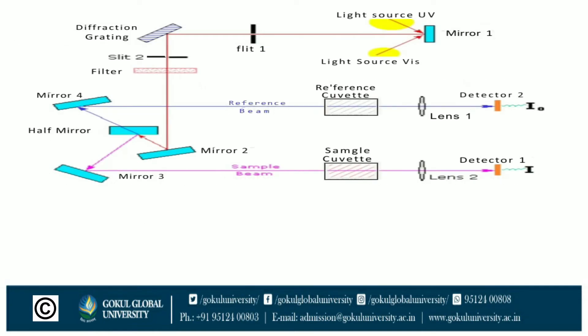In the double beam spectrophotometer diagram, UV light from the source is filtered by filter one, then diffracted by a diffraction grating and directed through mirrors two, three, and four. Here two beams occur: the reference beam passes through the reference cuvette and the sample beam passes through the sample cuvette. Both signals are collected by the detector and converted into the UV spectrum.